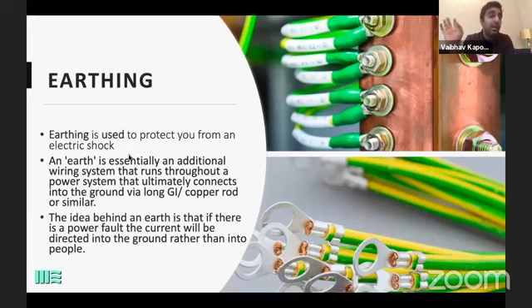I have seen as a power distribution company that the faults are so severe that the person has fallen on the ground. So when you're doing earthing of any metal structure, ultimately when the grounding is being done, it goes directly into the ground. So choosing the right amount of earthing, it could be your GI spikes or copper spikes, and the right size of wire for the earthing is very, very important for any electrical system, because that is not only to get you the right values, it is for human safety. It is for human safety.